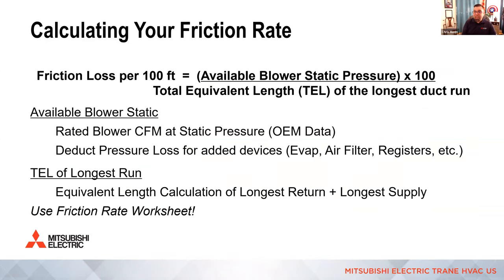So before I get rolling, when it comes to the math portion, I want to make sure everybody knows, I personally was taught some really bad rules of thumb when it comes to duct calculators. Now, of course, there's round and there's the rectangle slide rule style. Every time I would teach this class in person, people would bring their own, and I'd always see little marks by 0.1 or 0.08 because that was the rule of thumb they were taught.